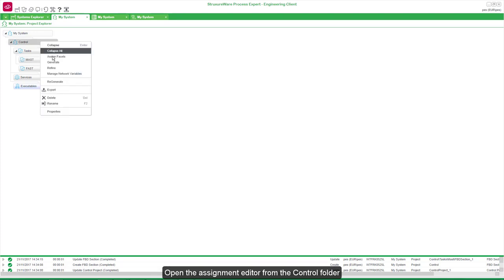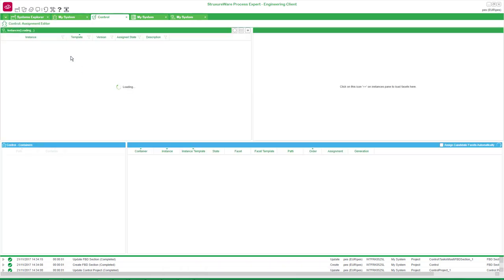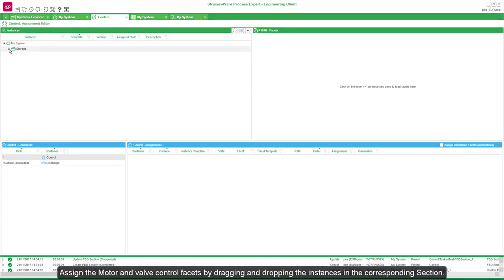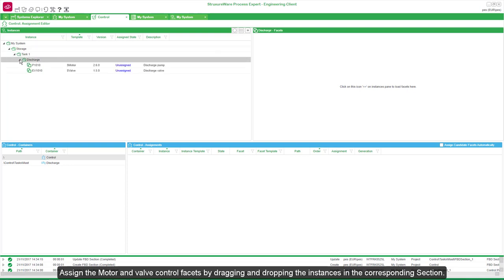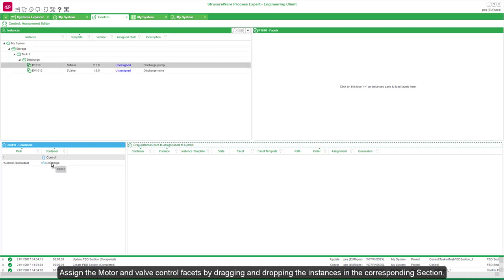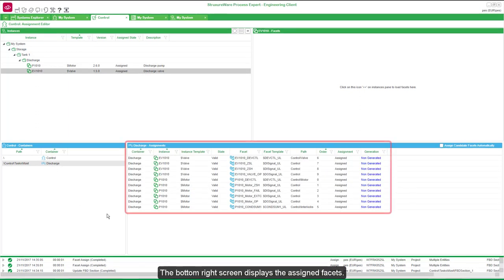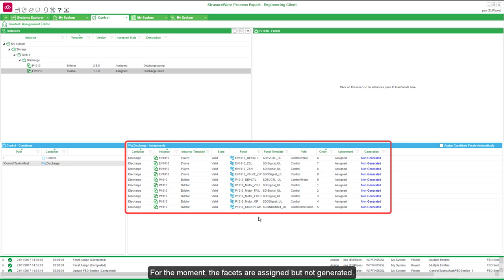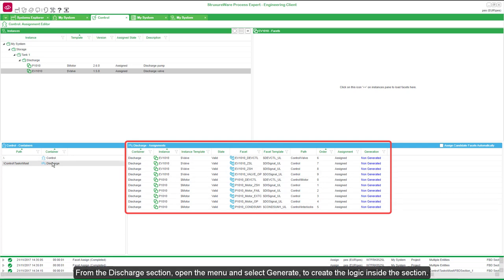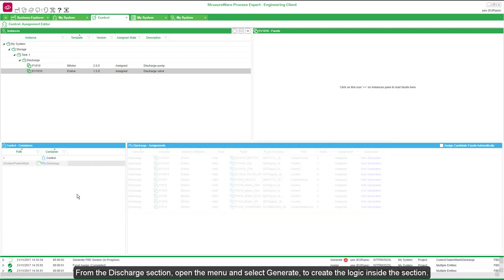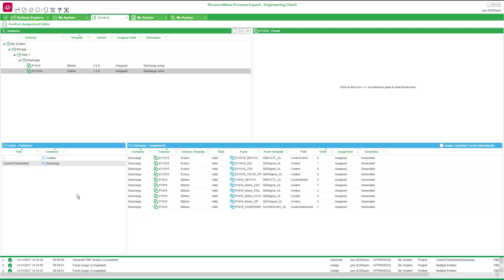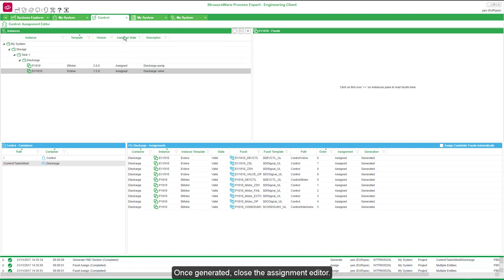Open the assignment editor from the Control folder. Assign the motor and valve control facets by dragging and dropping the instances into the corresponding section. The bottom right screen displays the assigned facets. For the moment, the facets are assigned but not generated. From the Discharge section, open the menu and select Generate to create the logic inside the section. Once generated, close the assignment editor.